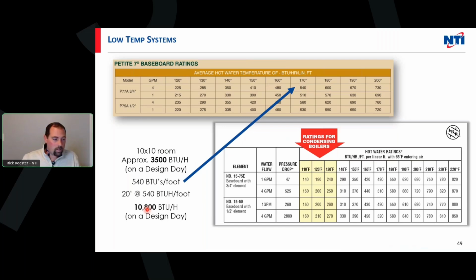So if I were to take that same 20 feet of baseboard, making no adjustments, not pulling any element out, not blocking any off, and all I do is change the water temp to 130 degrees supply and 110 return, that 20 feet of baseboard is now going to give out 4,500 BTUs, which is still 1,000 BTUs over the 3,500 I need on my design day. Now think about off of a design day, right? An average day in the 20s, 30s, 40s, depending on your region. On those average days, I don't need as many. I don't need 3,500. I might need 3,000, 2,500. Yet without modulation, like an inverter boiler or a modulating gas boiler, I'm always going to deliver 10,800, right?